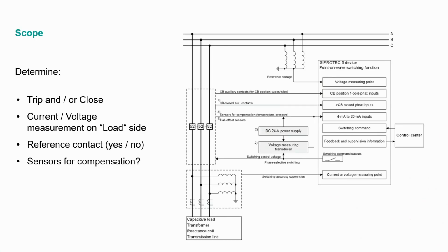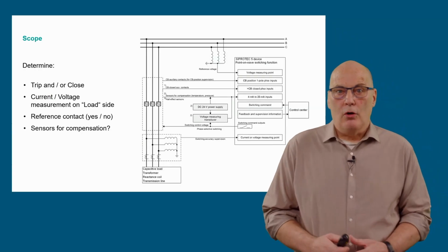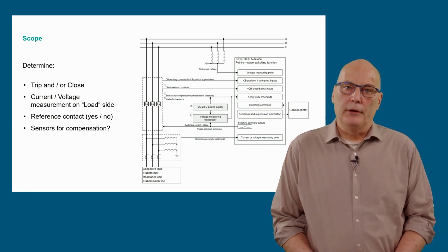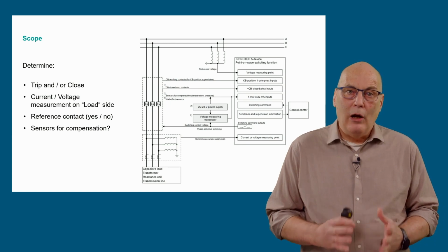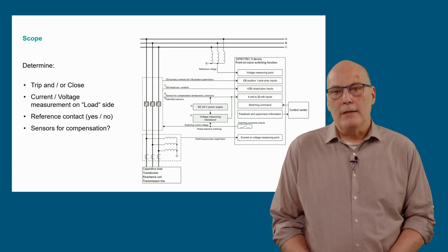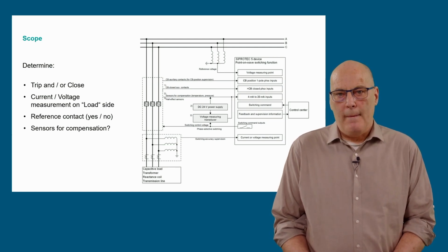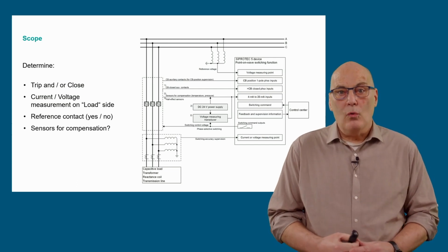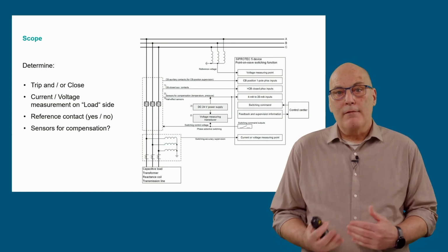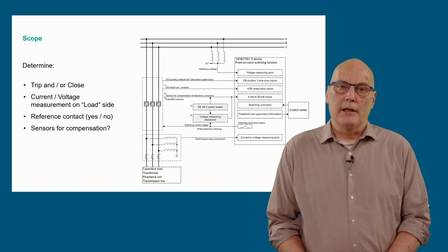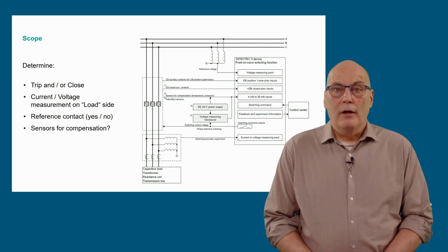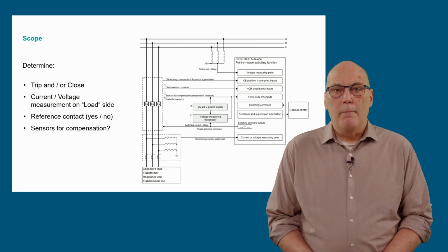Part of the determined scope of the application is, will point-on-wave be for closing and tripping or only for closing or tripping? Depending on the load, inductance, transformer or reactor, or capacitance, the load side measurement for monitoring the point-on-wave must be applied. With transformers, for example, a voltage measurement on the load side is used to monitor the closing. This is done because the current, only the magnetizing current, is too small to be used as a dependable criterion during point-on-wave closing. For capacitor loads on the other side, either current or voltage may be used. Here, the current is fairly constant and equal to full load current after energization. This monitoring current and or voltage is the transformer shown at the bottom of the diagram.